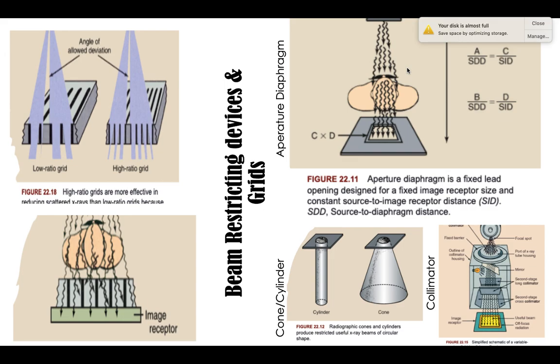Grids are used to reduce the amount of scatter radiation that exits the patient and reaches the image receptor. The primary purpose of a grid is to absorb scattered X-ray photons that don't carry image information, as well as allow image forming X-ray photons to pass through the grid and hit the image receptor. The more scatter a grid can absorb will lead to an image that has good contrast.